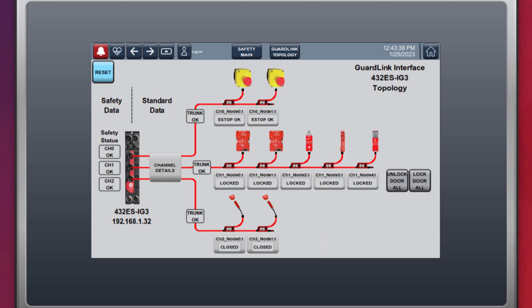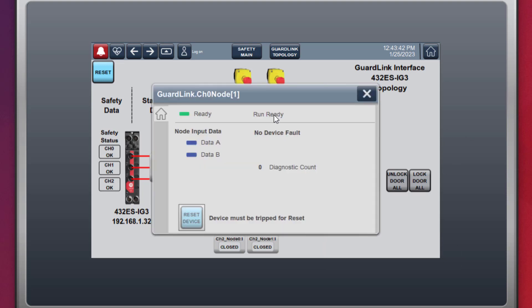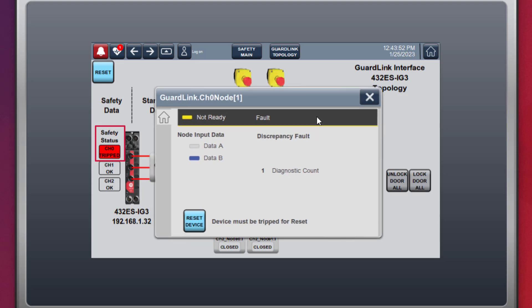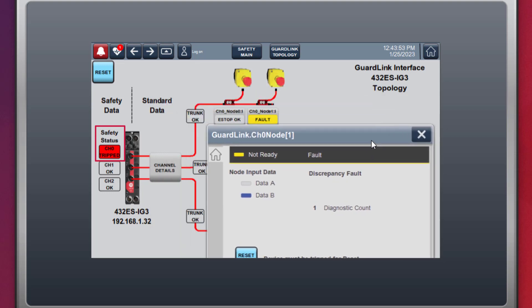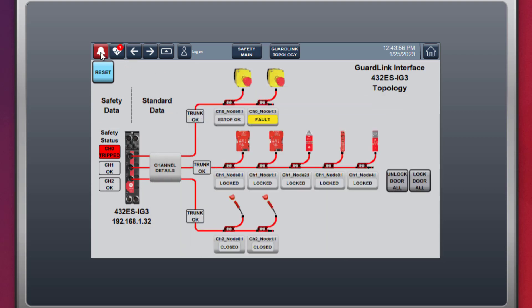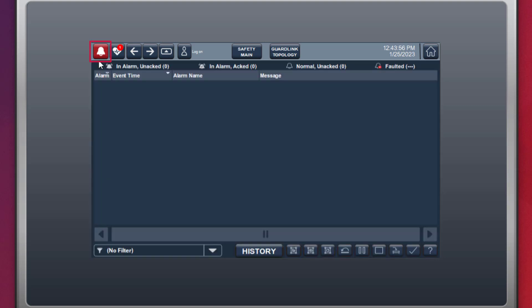While reviewing e-stops, observe what happens when one wire falls off of the dual-channel e-stop push button. Removing one wire from the e-stop push button causes the safety status of channel 0 to trip. A good programmer manually programs all alarms when a safety device is not ready. Click on the bell icon to see the node-specific alarm.